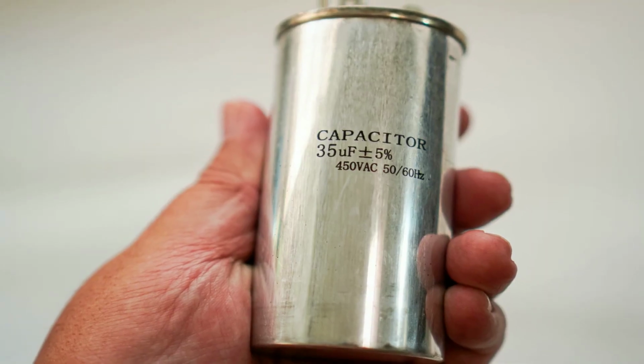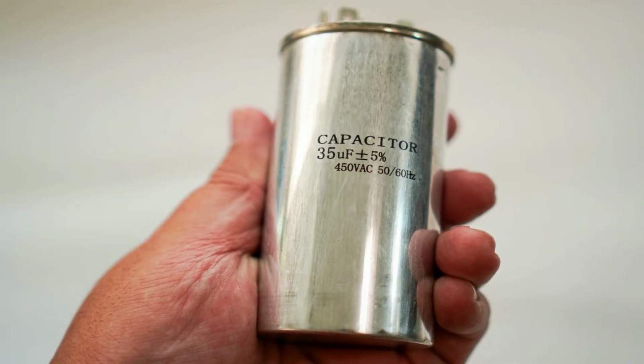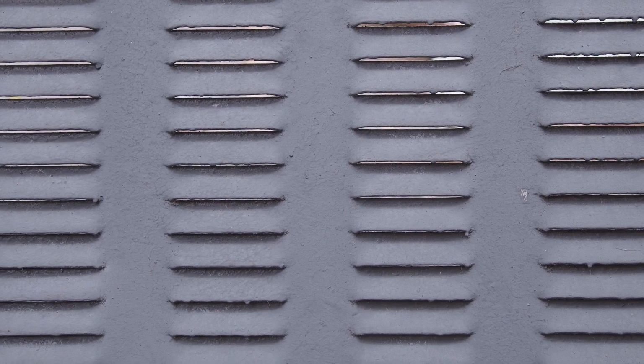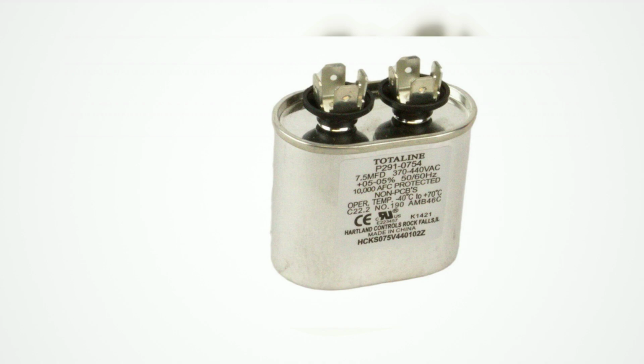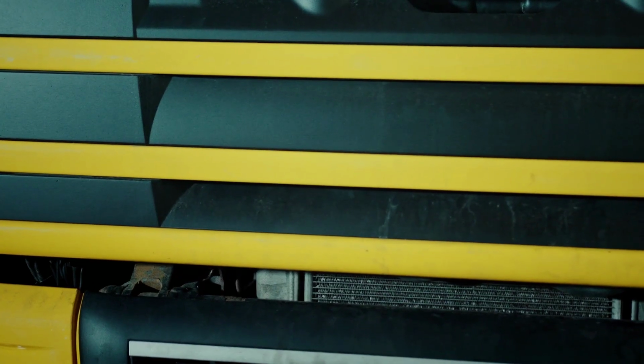The third specification is whether you need a single-run or dual-run unit. Most residential systems use a dual-run capacitor with 3 terminals labeled HERM, fan, and COM. Single-run capacitors have 2 terminals and handle 1 motor only. The old part will tell you which type you need, where to find your specs. The label on the old capacitor is the primary source.